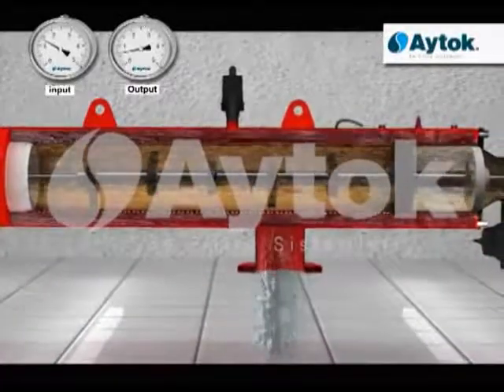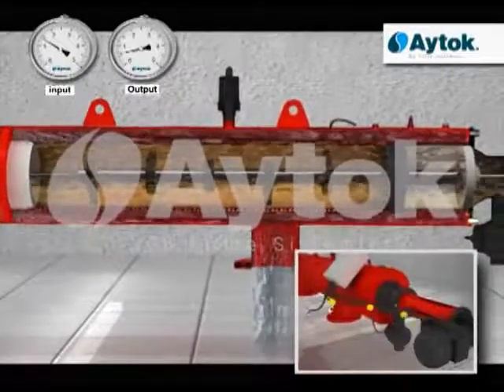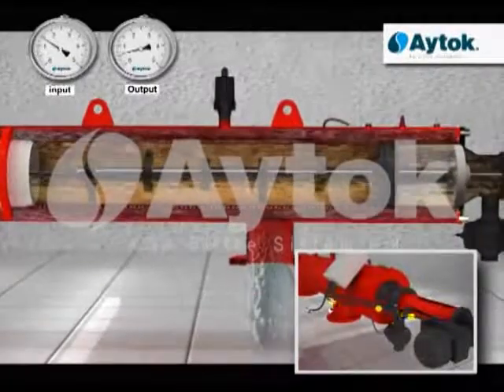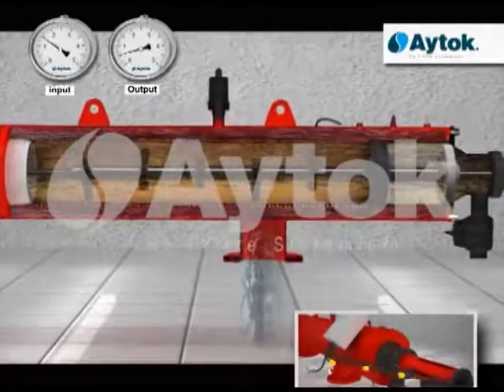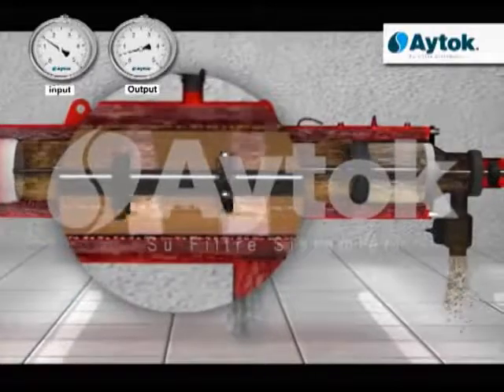The hydraulic and/or electronic control unit opens the discharge valve with the signals it sends at this value and performs a backwashing flow that reaches the atmosphere. This makes a vacuum effect in the flow nozzles, and the nozzles absorb dirt on the fine sieve.